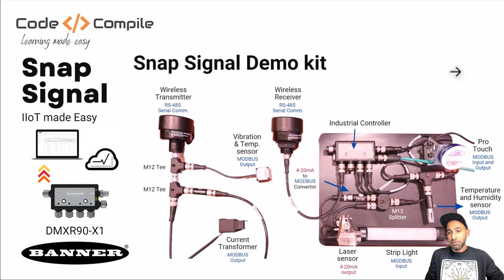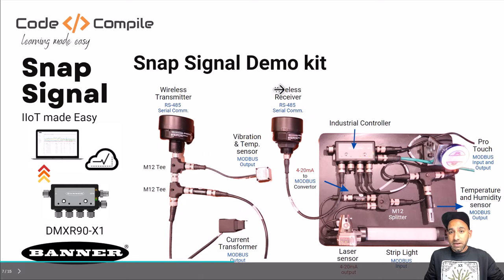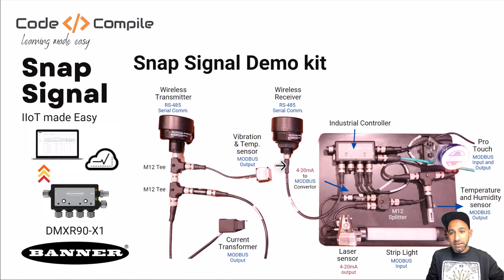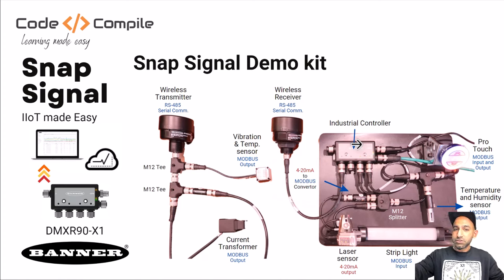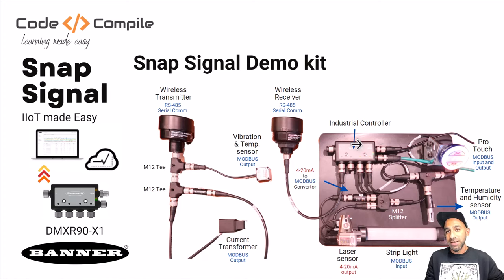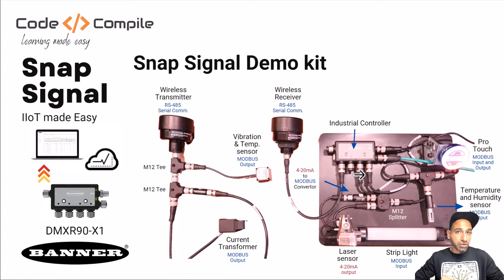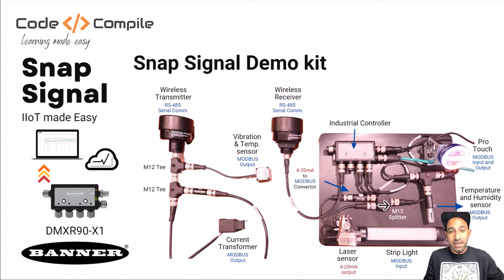In this video, first I'm going to introduce my kit. I have a wireless transmitter and receiver — the wireless transmitter is transmitting data from my vibration sensor and current transformer, and the wireless receiver is receiving this data and sending it to one port of my industrial controller. Both devices are actually the same, but by changing the dip switches you can change their functions. The next two ports are connected to a laser sensor, strip light, and the other to a pro touch and temperature humidity sensor. Using M12 splitter and M12T connectors, you can split your signals and have multiple devices connected to the same port.